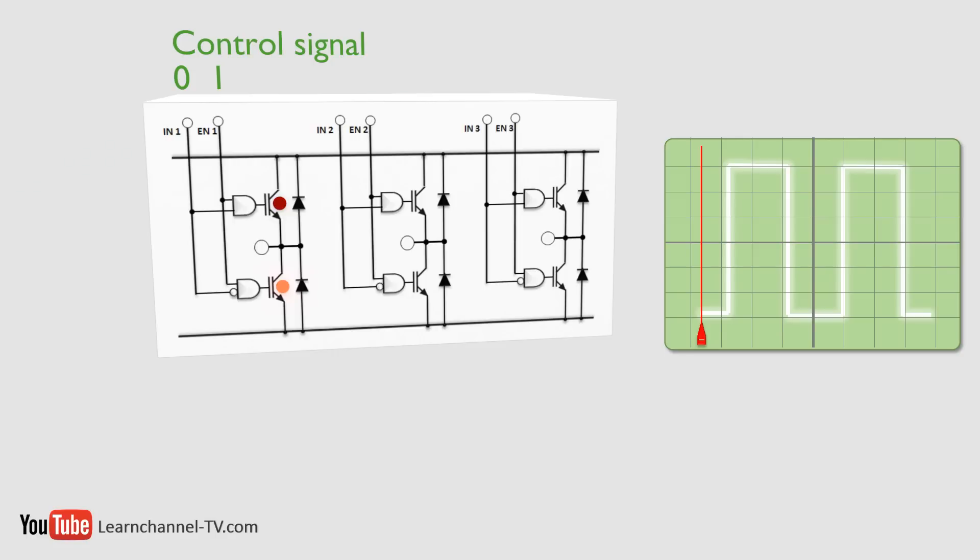Concerning the technical implementation of the inverter, electronic switches are used, in this case IGBTs. In order to avoid a short circuit, their control connections are interlocked. The diode serves as a freewheeling diode since the motor coil is an inductance.